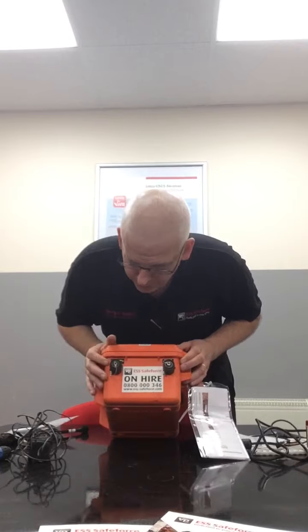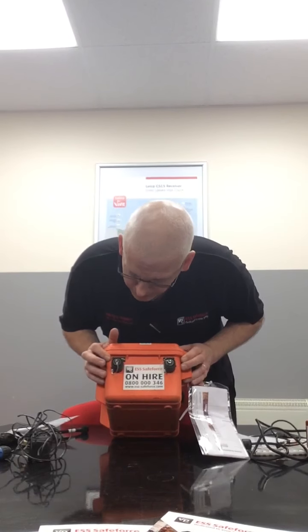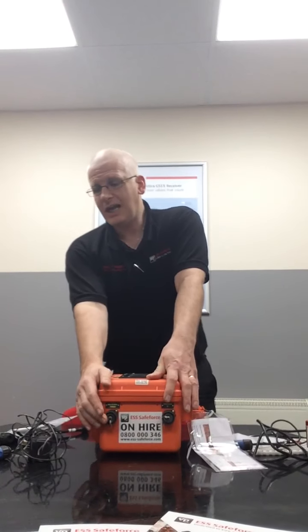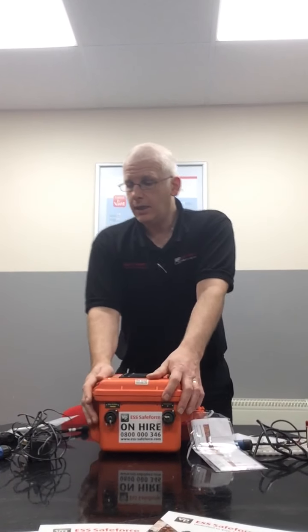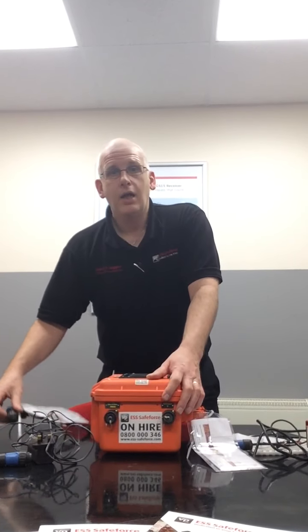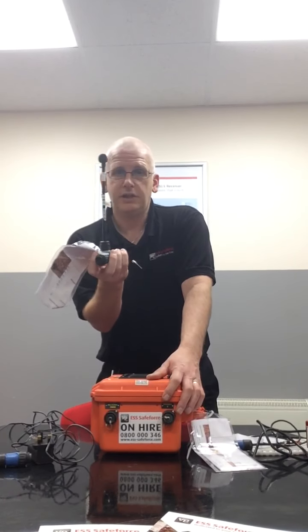Looking at the unit a bit closer, if we turn it to the side here, you'll see we've got two connection points. This one here is labelled MIC alarm power. That connection has three uses ultimately. Power, for the mains to go in if you need to power it up by mains. MIC for microphone, so if you need to use the aero pressure microphone, and also as an optional accessory we do an audible alarm which can be plugged in there as well. So that's that connection.